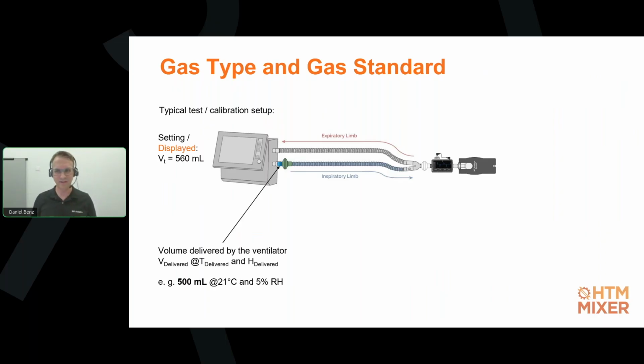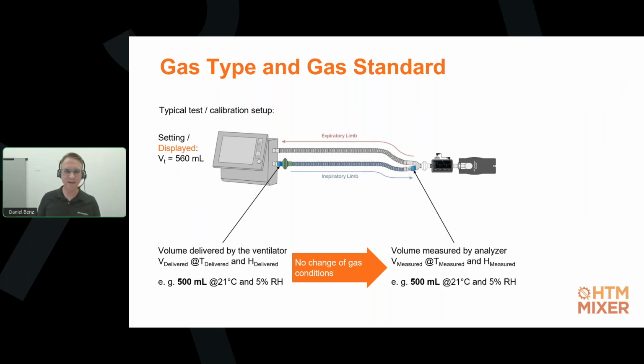So even though we set 560, it's going to deliver just about 500 milliliters, because it considers an increase of the volume in the patient circuit system caused by an increase of the gas temperature and humidity as it travels along the circuit until it reaches the patient. However, unlike in our previously discussed real-life patient scenario, in our test setup we typically don't have a humidifier and a heated limb. So our gas condition is not going to change. We don't have the increase in temperature and humidity. That means the same 500 mLs delivered by the ventilator are going to end up on our measurement device, our gas flow analyzer.